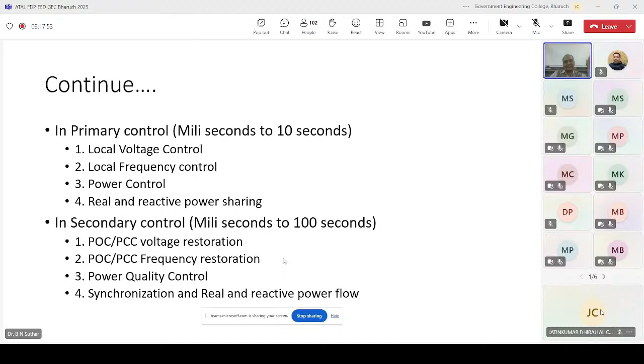When we talk about the time frame, the primary controller should operate first, within milliseconds up to 10 seconds. After that comes the secondary control, which should be able to operate within milliseconds up to 100 seconds.